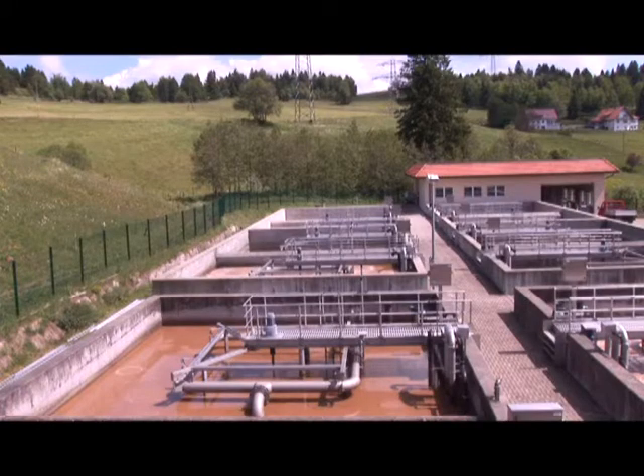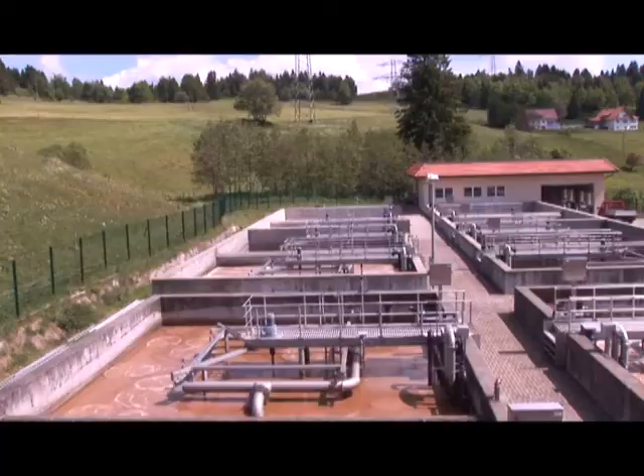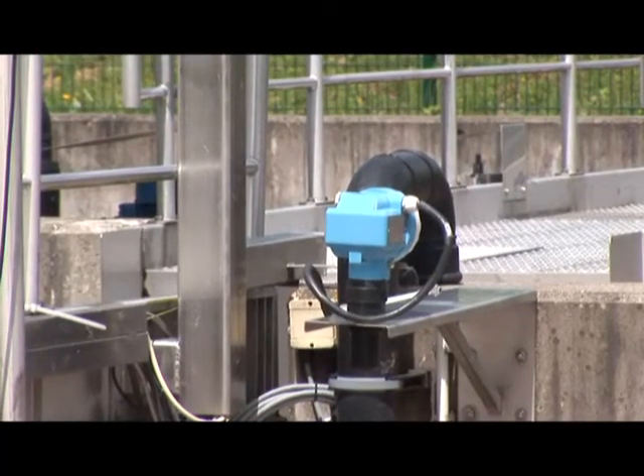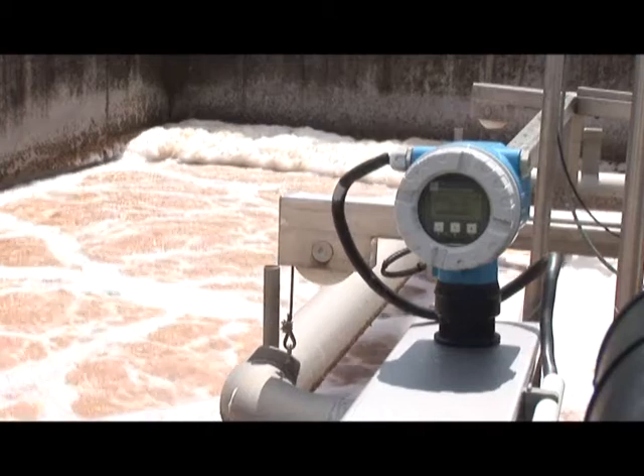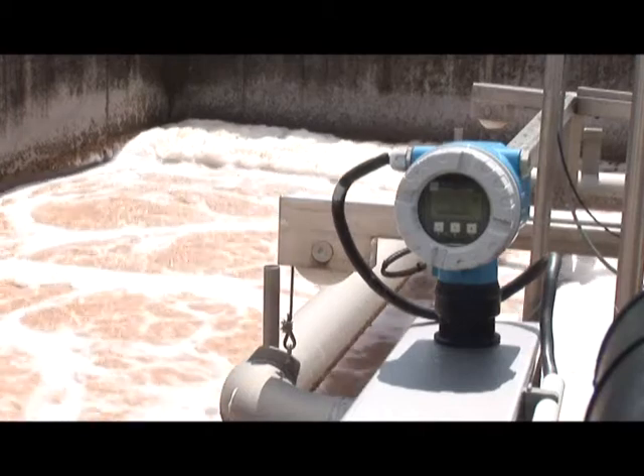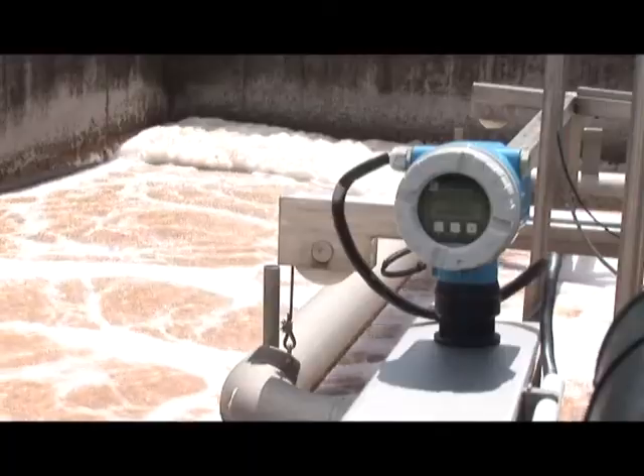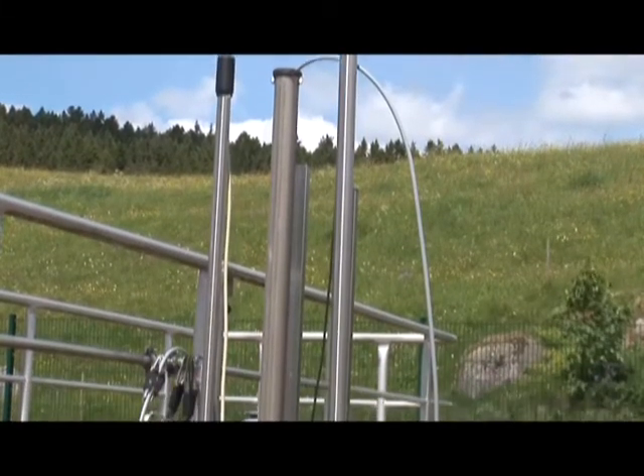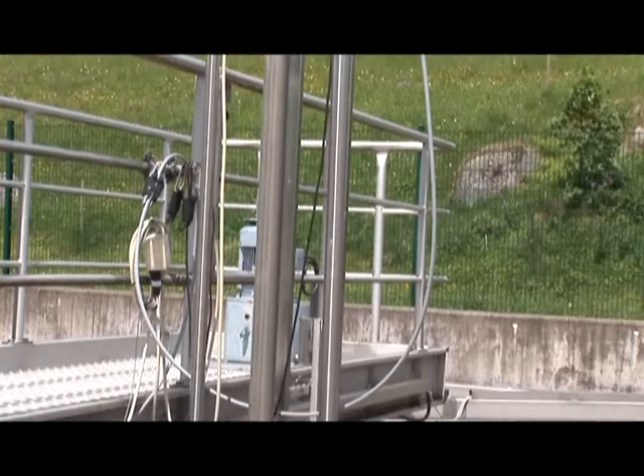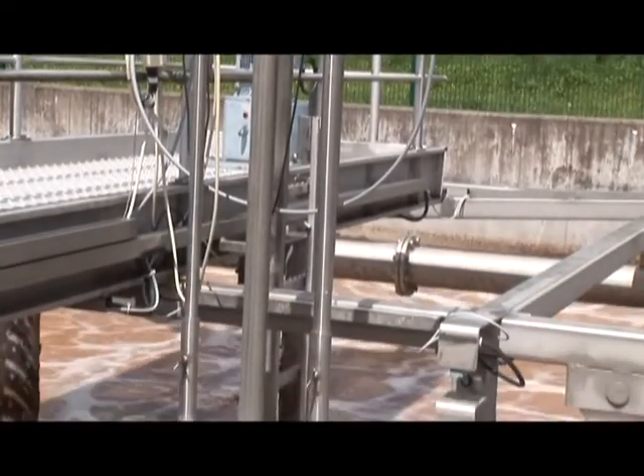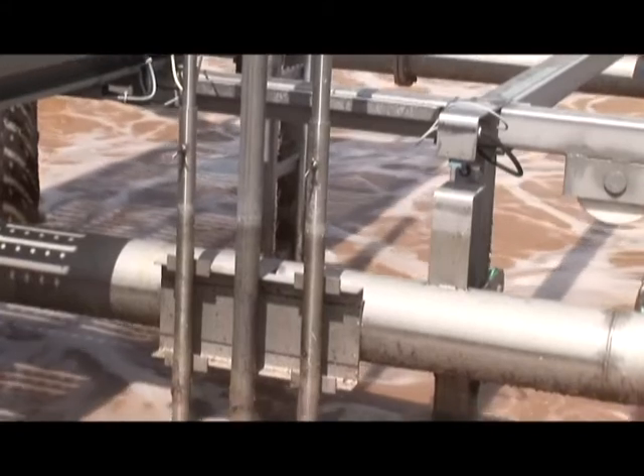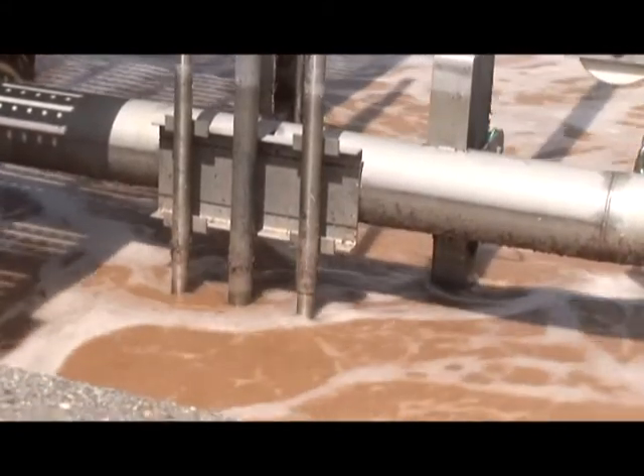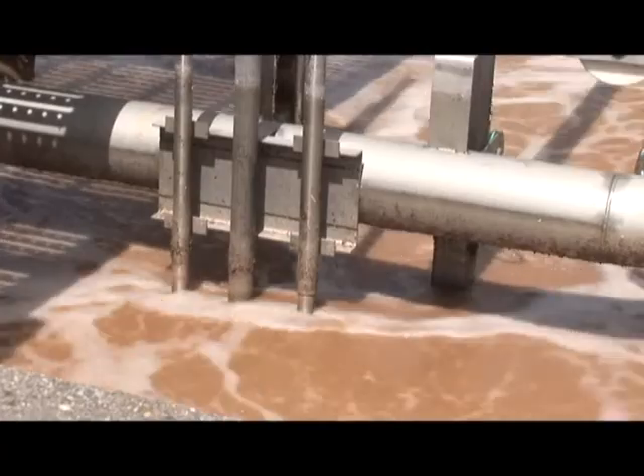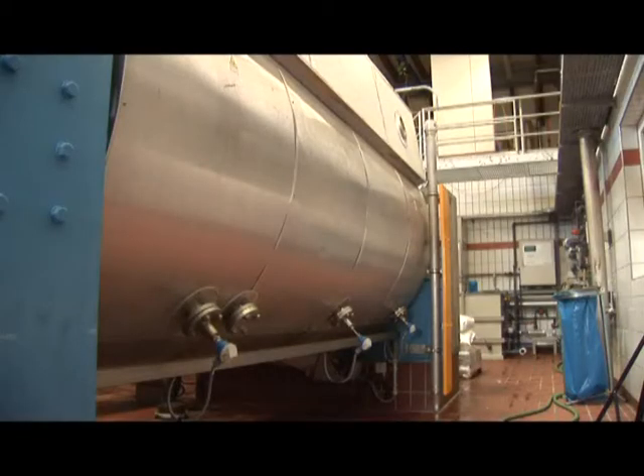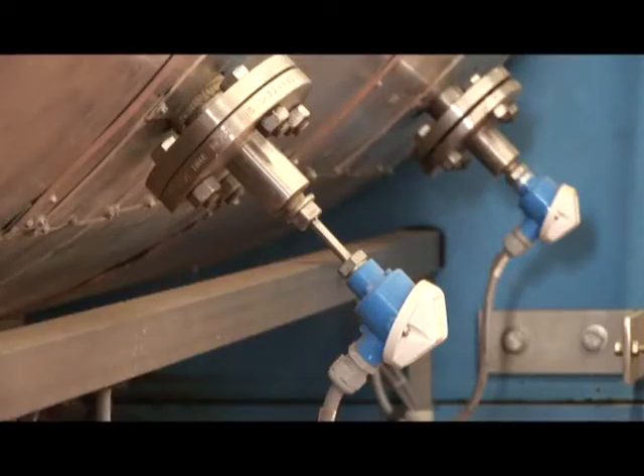In the SBR, the wastewater is aerated and left to sit, so that the sludge can precipitate out. In order to determine the level, a Prosonic M ultrasound sensor is used for each SBR. There is a pressure measurement device in the tanks to carry out hydrostatic measurement. Oxygen measurement and optical turbidity measurement are installed here in order to determine the current load of solids. The sludge dryer has 3 temperature sensors which monitor drying temperatures.